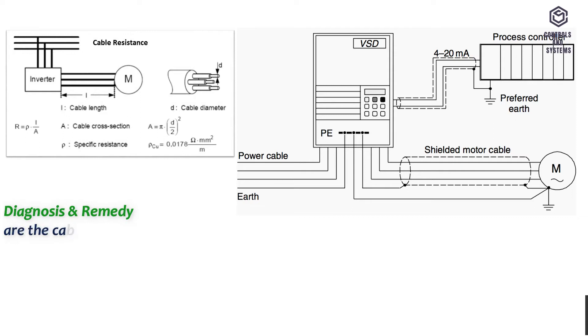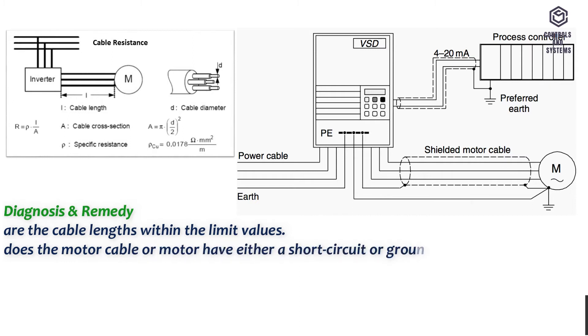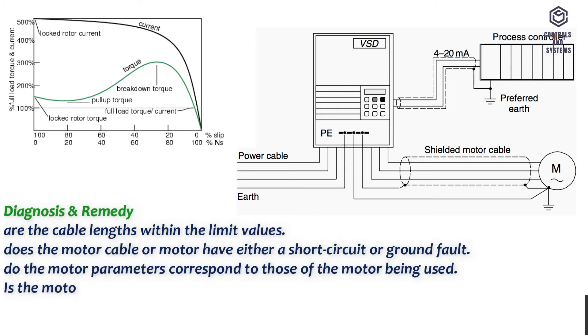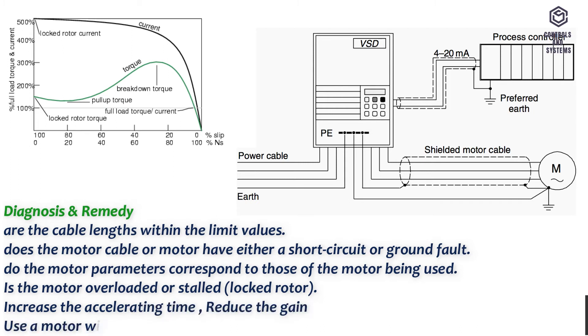Diagnosis and remedy: Are the cable lengths within the limit values? Does the motor cable or motor have either a short circuit or ground fault? Do the motor parameters correspond to those of the motor being used? Is the motor overloaded or stalled, locked rotor? Increase the accelerating time. Reduce the gain. Use a motor with a lower power rating. Is the stator resistance value P0350 correct?